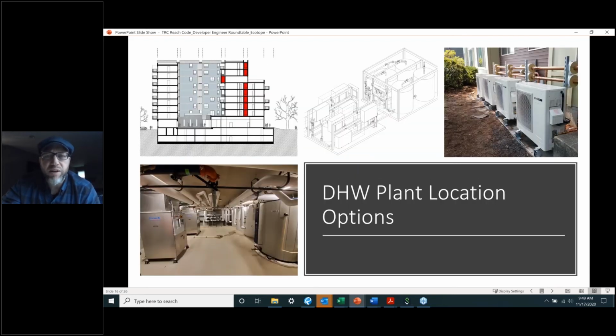Next consideration would be where you're going to decide to put your plants. I see a lot of domestic hot water plants in California on the roof. We've done rooftop installs, and we've got a kind of skid product we're working with Sandin, or Senko, to develop—plug and play devices that would just get craned up to the roof and plugged in. We've also done ground mount, just on the outside of a building with an adjacent mechanical room, and we've done in the garage. Over on the left, you can see we've got a big space down in a parking garage. This is a 360 unit plant here, with lots of storage and some big Colmac CXA heat pumps.